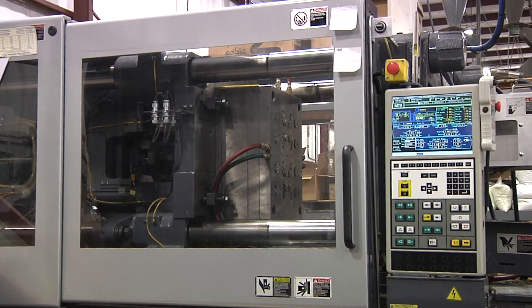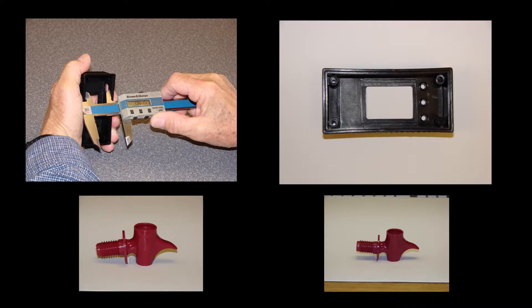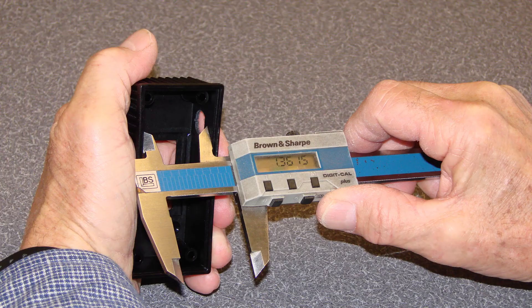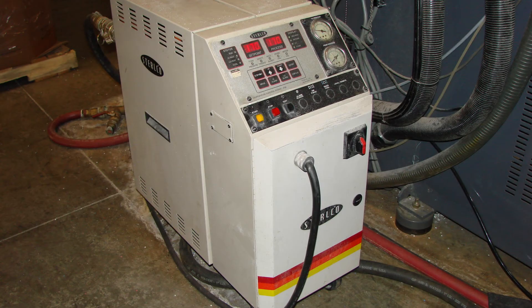Often, successful molding of a part requires multiple temperature zones within a single mold. Complex part geometry can result in poor cooling in localized areas of the mold, resulting in part warpage or poor dimensional control. Some parts require different A and B side temperatures to control where the part sticks. The conventional solution to these cases is the use of traditional mold heaters, generically called thermolators, to elevate steel temperatures where needed.